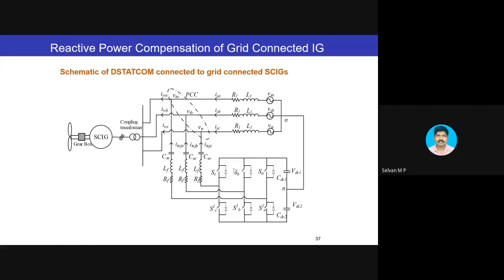Where is it used? Mostly in wind farms with SCIG, squirrel cage induction machine based wind farms, we can use this STATCOM for compensating reactive power. Why? An SCIG based system needs reactive power compensation because it is a squirrel cage induction machine. It is going to give you real power when the wind speed is higher than the cut-in speed. Definitely it is going to give you real power.